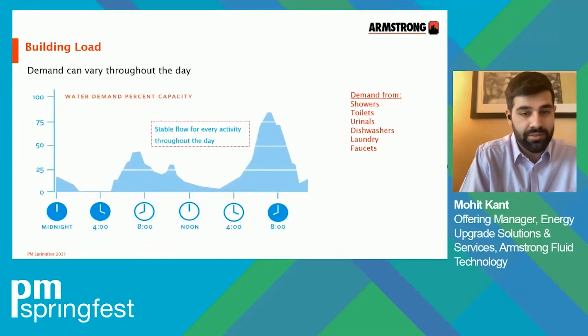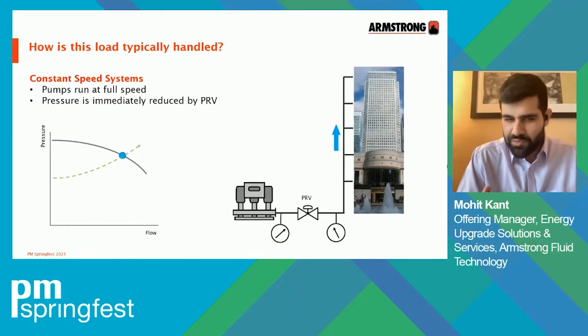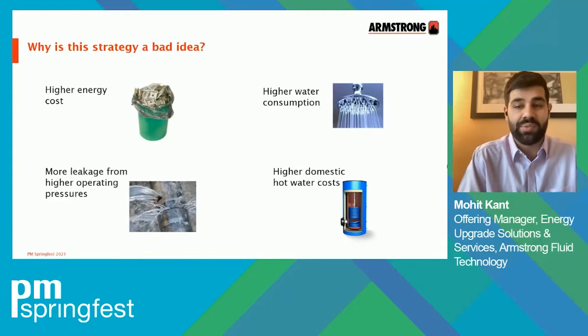Traditional booster pump systems maintain a constant pressure supply to the building via a pressure reducing valve or PRV. This configuration is called constant speed because the booster pumps run at full capacity to increase the water pressure, and then the pressure is immediately reduced by the PRV. So why is this strategy a bad idea? The water pressure to the building stays constant, but the utility bills are much higher than necessary. Constant speed systems also consume excess water through flow and leakage associated with higher operating pressures. Additionally, maintenance for such equipment is expensive due to high runtimes leading to maximum wear and tear, as well as really high PRV maintenance costs.